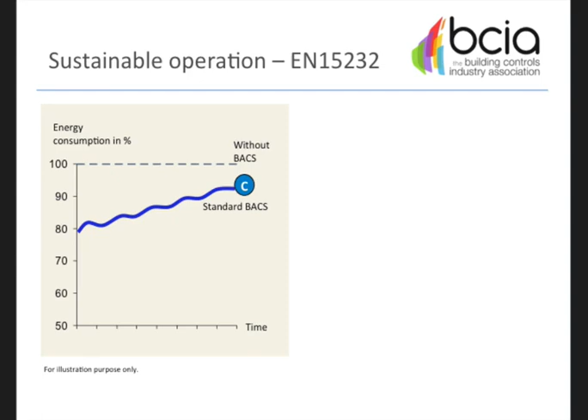If we can get in at the design stage, as I mentioned earlier, and install an advanced integrated building automation control system, our starting point is much lower, but energy prices will still rise - it's a fact. So what we suggest is a functional assessment, a check to make sure the equipment is running correctly, the building hasn't changed, the loading is the same, and the plant is up to the design criteria. If we carry out this functional check, we create a sawtooth in our energy bill through recommissioning - recommission, recommission, and recommission.